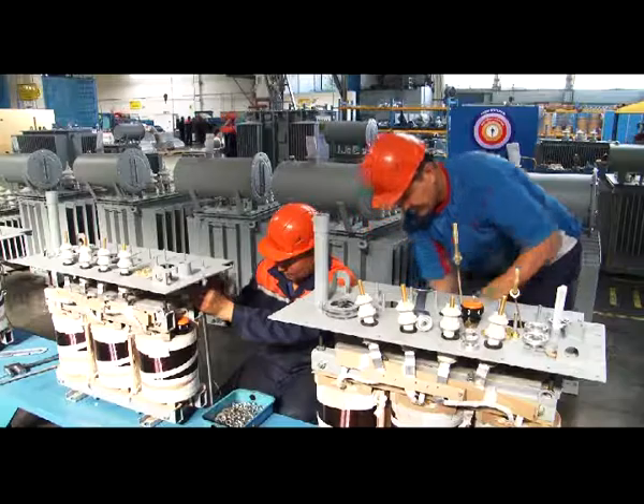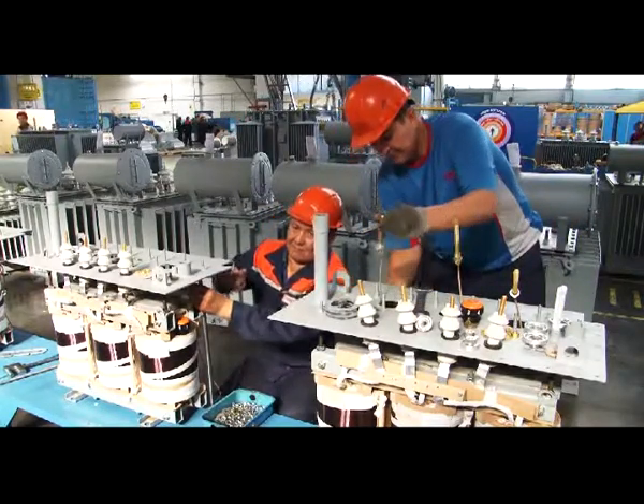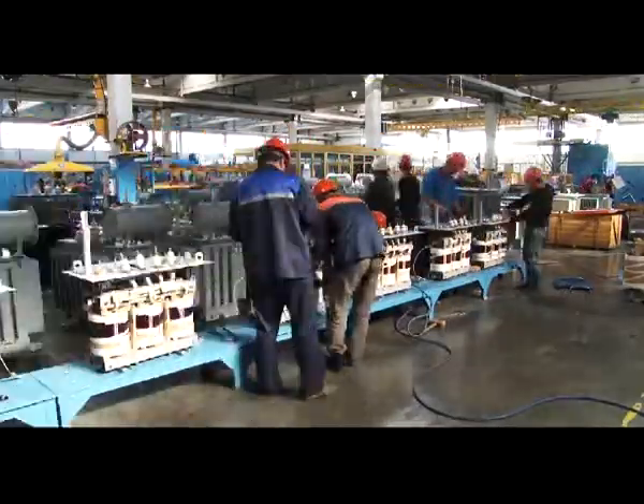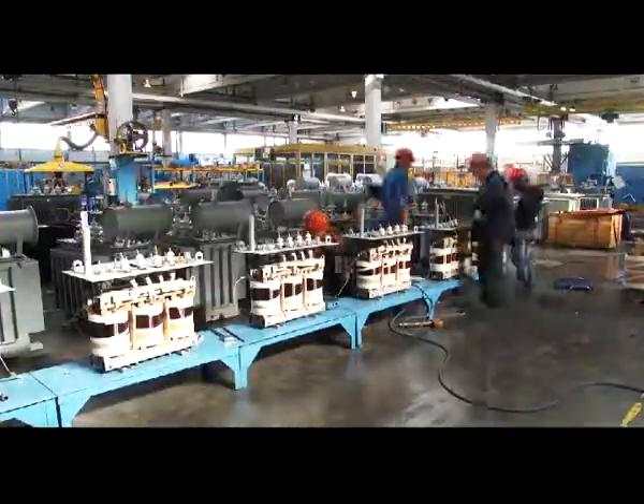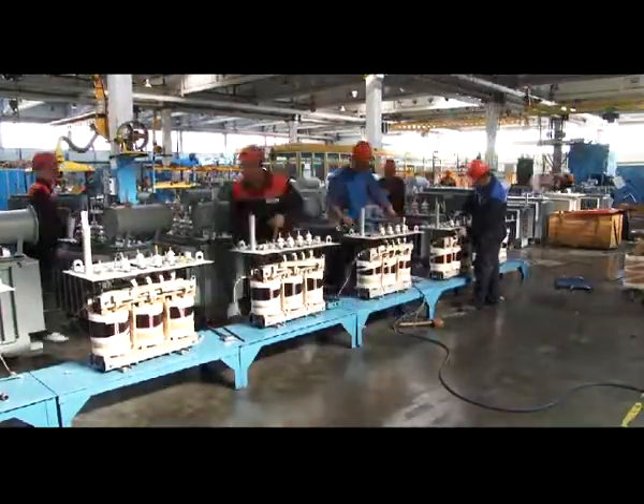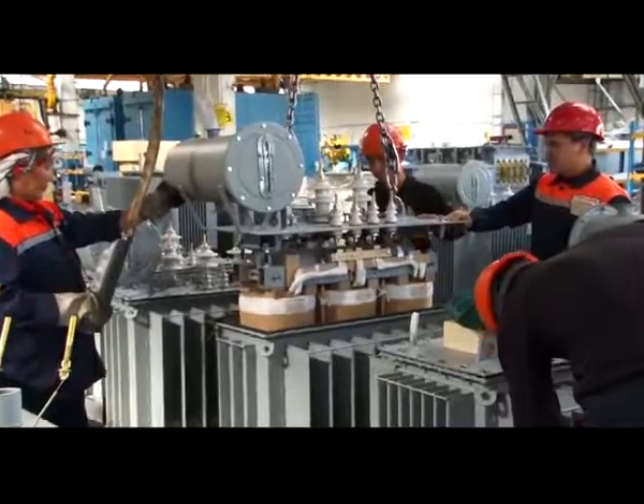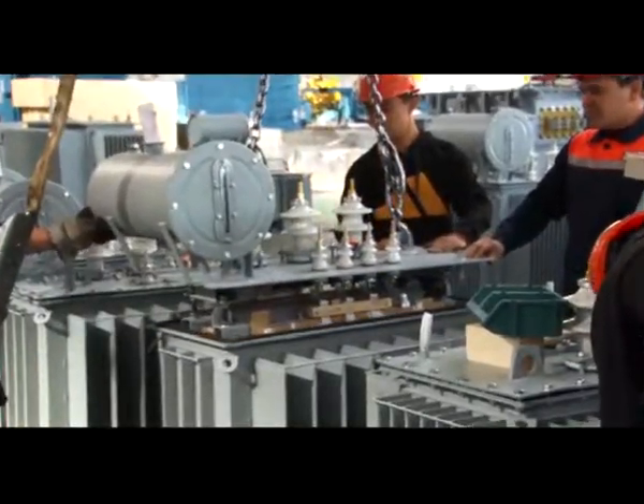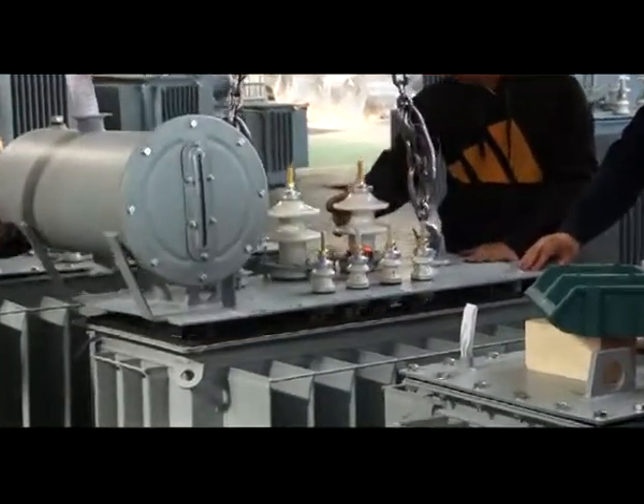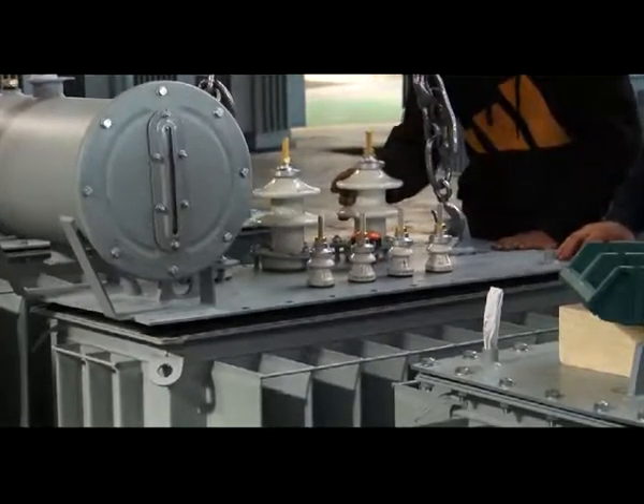From the furnace, the magnets are sent to the third stage of assembly, the final stage. Here the magnetic core and winding are fastened once again, including all the bolts and screws. The top of the tank is attached to the active part, and all the outputs are closed off with ceramic isolators. Then the magnet with the top is inserted into the tank of the transformer.